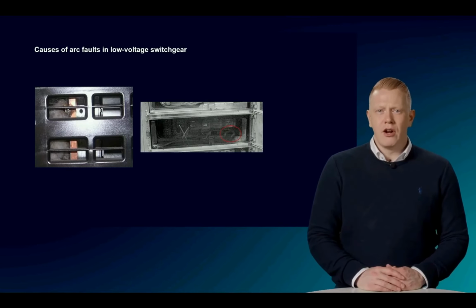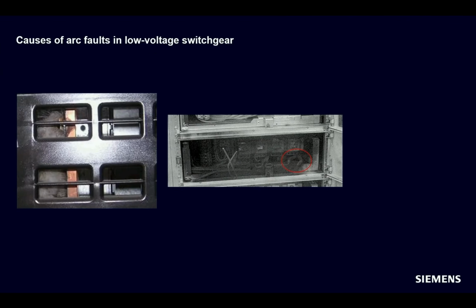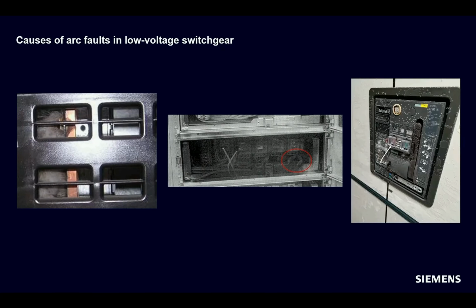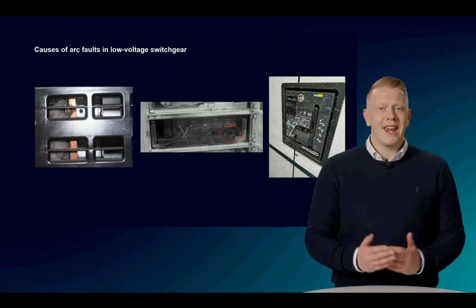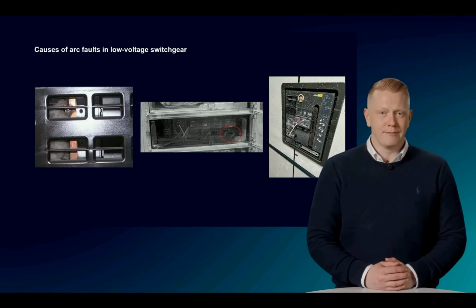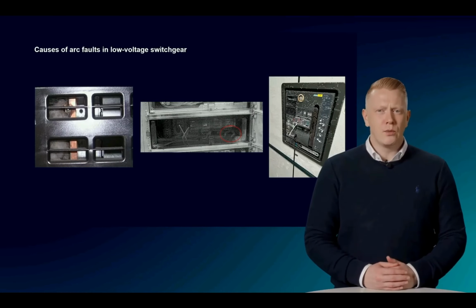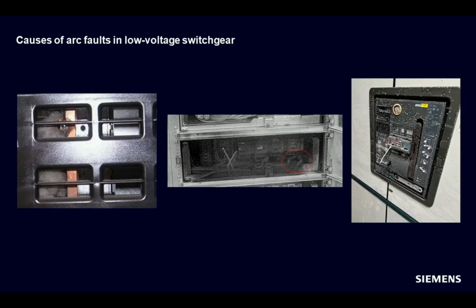However, handling errors are also a possible source of risk. For example, incorrectly carried out maintenance work or non-compliance with the environmental conditions for which the system is designed. Like in this example, a system that stood in a building without windows and heating and is iced over. Last but not least, errors in planning also pose a further risk, for example, due to incorrect dimensioning of equipment or cables. In an extreme case, this can lead to an overload of the components, which can then lead to failure and also to short circuit. And this means an arc fault.